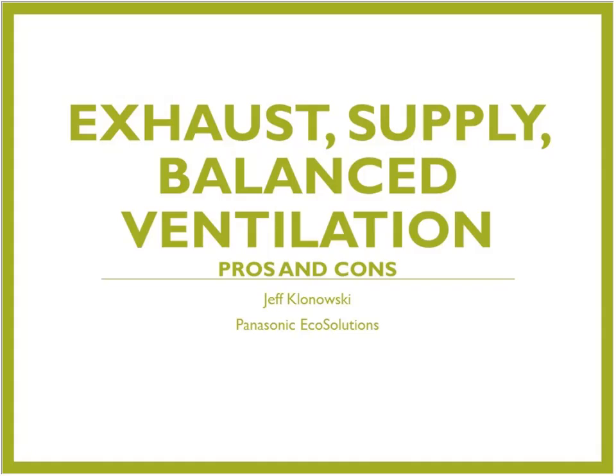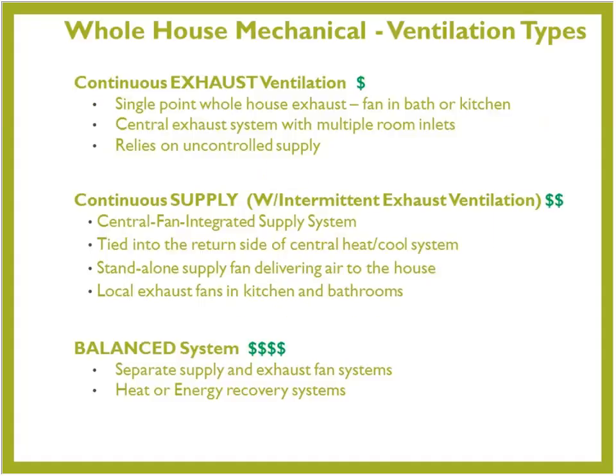All right, so if we all agree that we have to ventilate and can agree that we want to reduce some static pressure, let's talk about the three different types of ventilation that we can use. We can use exhaust, supply, and balanced ventilation. And let's talk about some of the benefits of each of those. And note, too, that I've got here some cost indicators as to each of these systems. As we go through each of them, understand that your cost is going to go up as we move from exhaust only to supply to balanced. And I'll explain why that is as we go through each one.